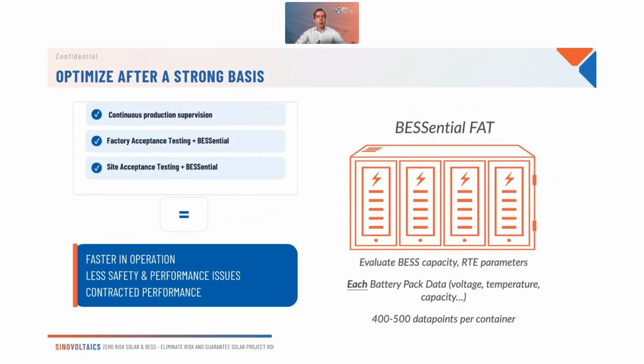Of course you start with the contracts, and when you actually start with the manufacturing of the battery, inverter, transformer, and so on, that's where faults or underperformance issues can start. So what we do, for example with batteries, is production supervision and monitoring, meaning that when the manufacturer is manufacturing the batteries and installing the modules into racks and containers, we are there to see every step of that manufacturing process, to see that no shortcuts are taken, everything is smoothly installed, thus preventing mistakes before the product reaches the end of line.